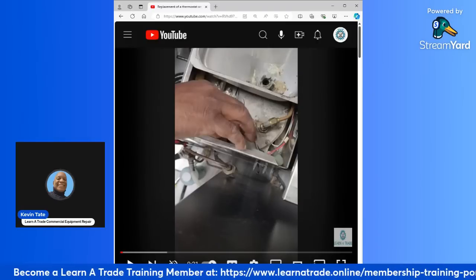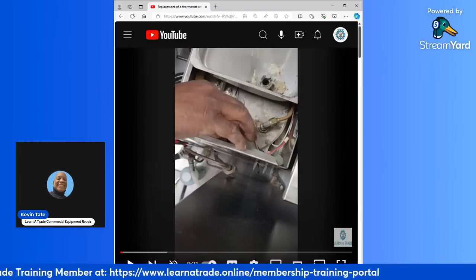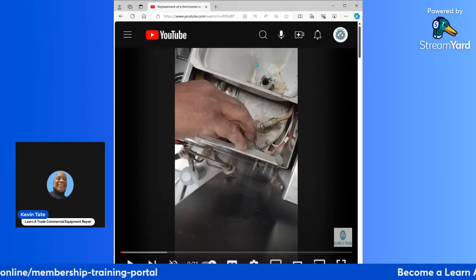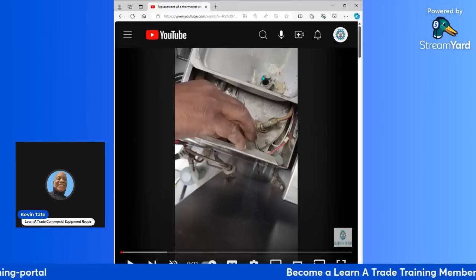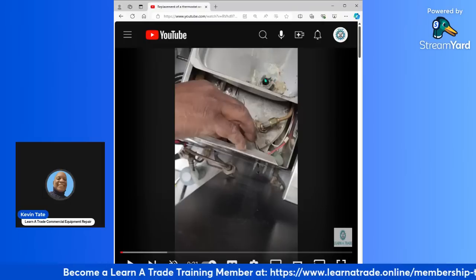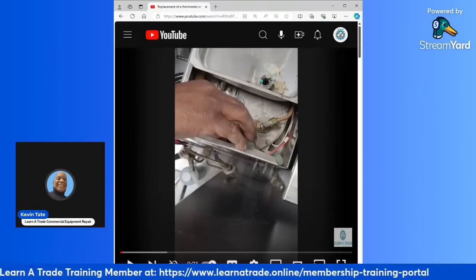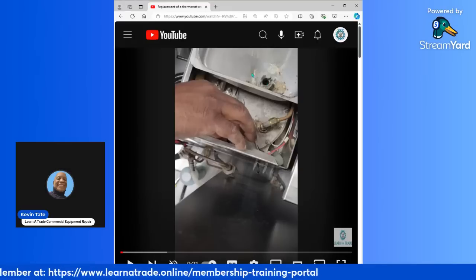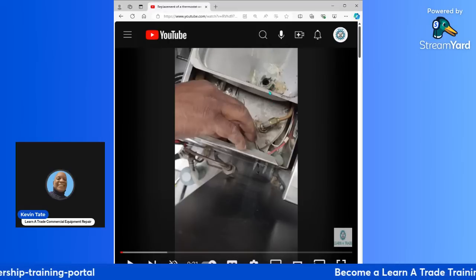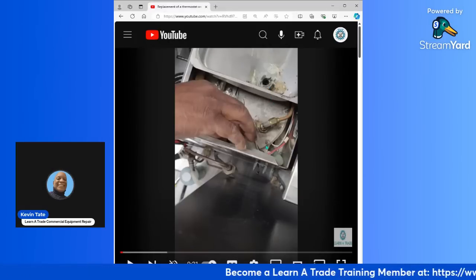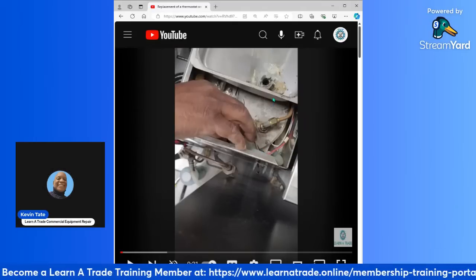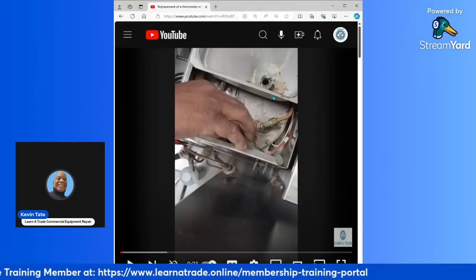Right there, I'm removing the water inlet tube from the drain pan up here, the water pan, so that I can remove this bolt holder, nut holder right here. This secures the pan to the hot water tank at the top, so I'm going to end up pulling that out. I'm just setting the inlet water line aside. The inlet water line goes into a port right up here on the water pan.